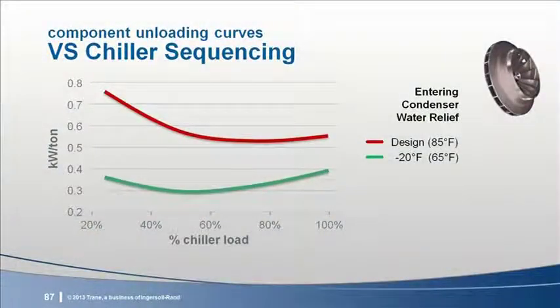But what about at other operating conditions, namely lower lifts? Here, we see the unloading curve with a 20-degree decrease in entering condenser water temperature. The curve not only drops, but it cants downward to the left. At this condition, one chiller at 100% load operates at 0.39 kW per ton, while if 2 chillers were running at 50% load, their performance would be 0.30 kW per ton. This represents a 23% reduction in chiller energy use for the same system load.